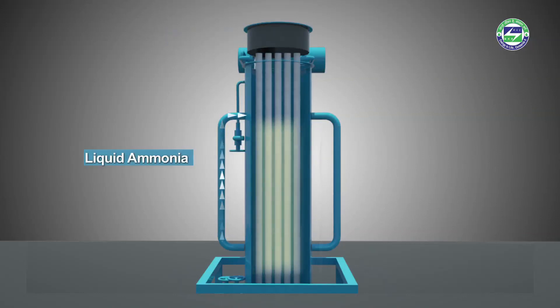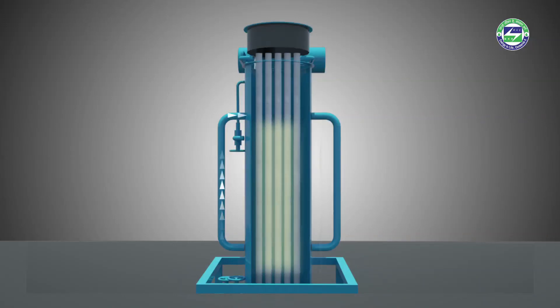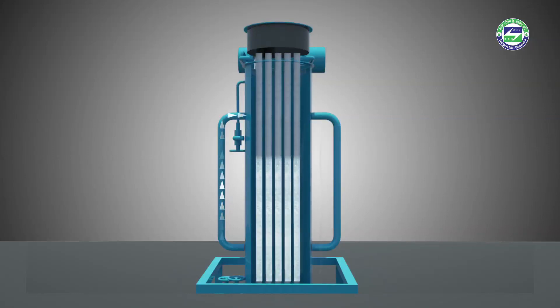The freezing process starts with ammonia being pumped from the freezer into the condensing system. Liquid ammonia then flows from the condensing system back to the freezer, and water is constantly recirculated through the vertical tubes of the freezer. Ice forms on the inside of the freezer tubes.